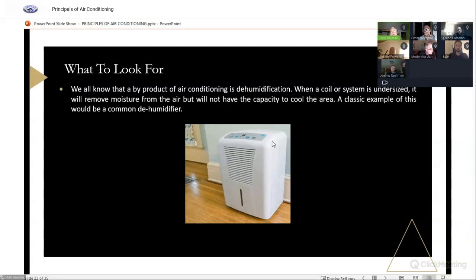A dehumidifier is an undersized air conditioning system. It can't cool the room that it's working in, but it will take the moisture out. It'll dry it out. So that's a small system, grossly undersized. It'll still dehumidify, but it's not going to cool. It's a small air conditioning system. It needs to be cleaned. The coils can get dirty. It can freeze up just like any other unit. But that's an example of an undersized unit.